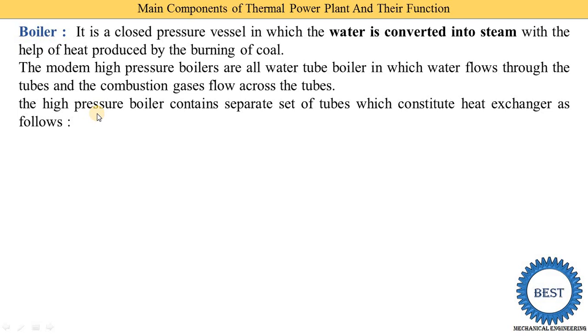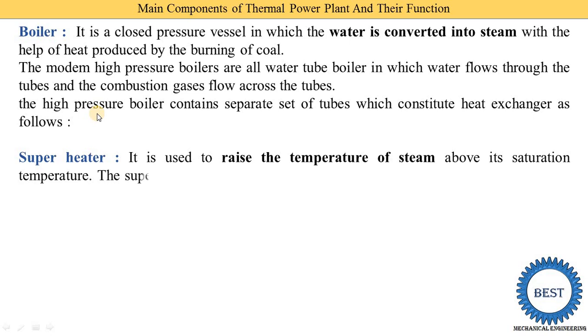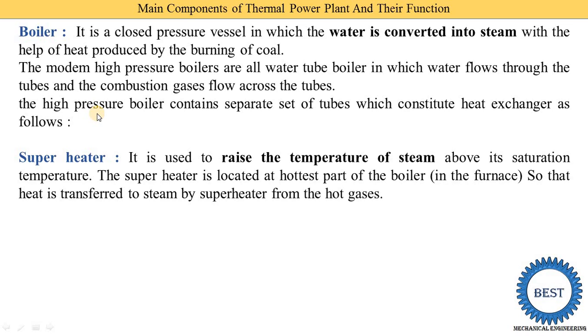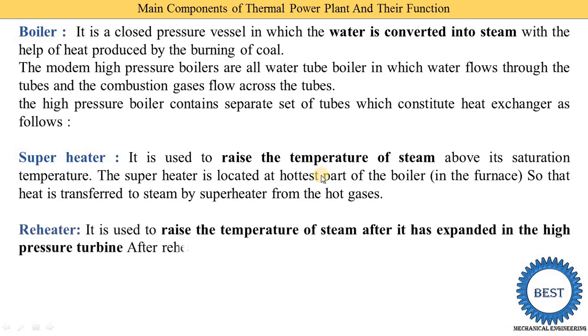First we understand the superheater. The superheater is installed after the boiler — the steam coming out from the boiler is supplied to the superheater. In the superheater, the temperature of steam is raised above its saturation temperature, which is why it is called the superheater. It is located at the hottest part of the boiler so that heat is transferred to the steam from the hot gases.